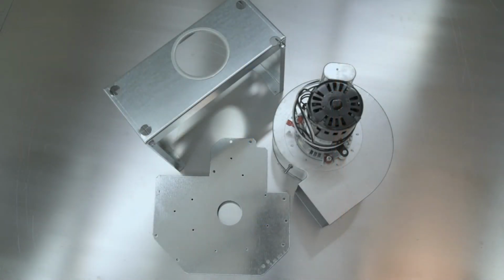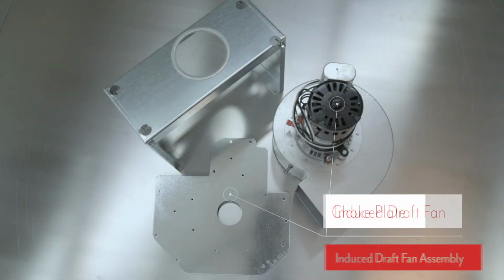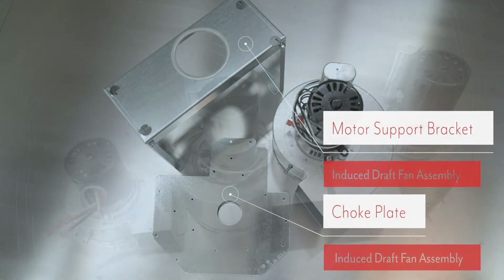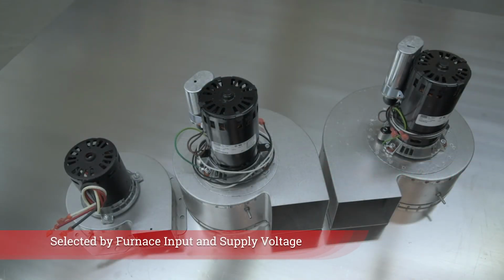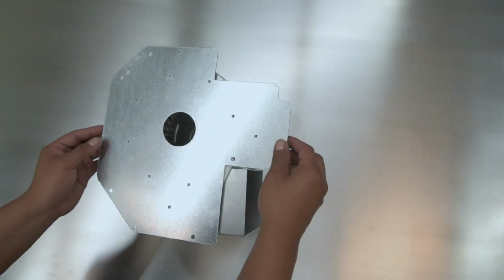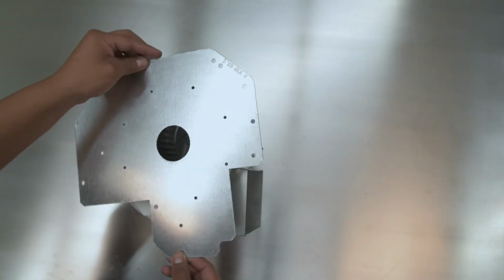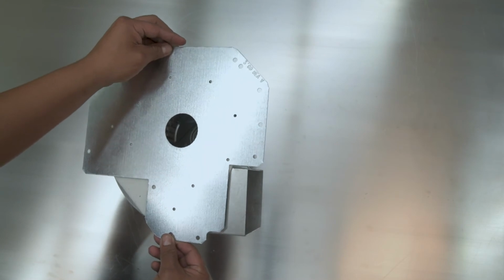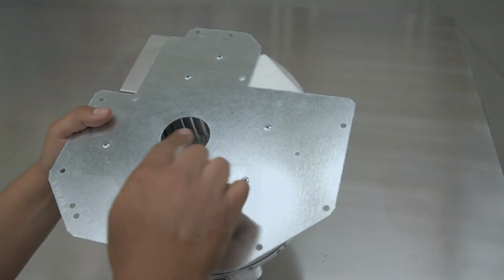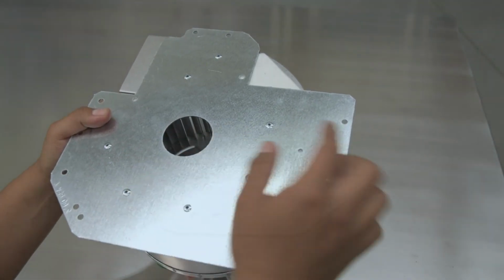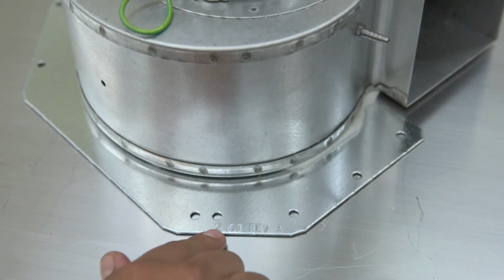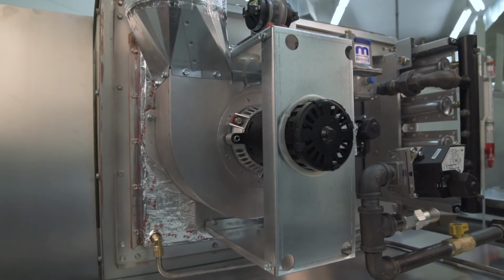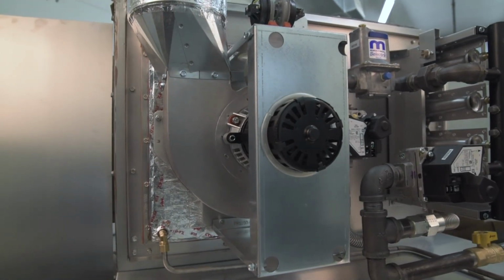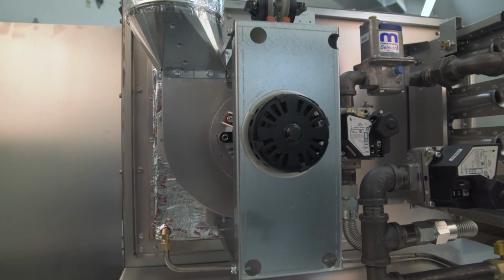The induced draft fan assembly consists of an induced draft fan, choke plate, and motor support bracket. The induced draft fan is selected based on the furnace input and supply voltage. The choke plate's purpose is to control the amount of combustion air that is drawn through the burner tray. The plate opening directly affects the combustion flue gas values. Choke plate sizes are based on furnace BTU input. The motor support bracket is fastened into position for the purpose of ensuring the correct inducer motor alignment.